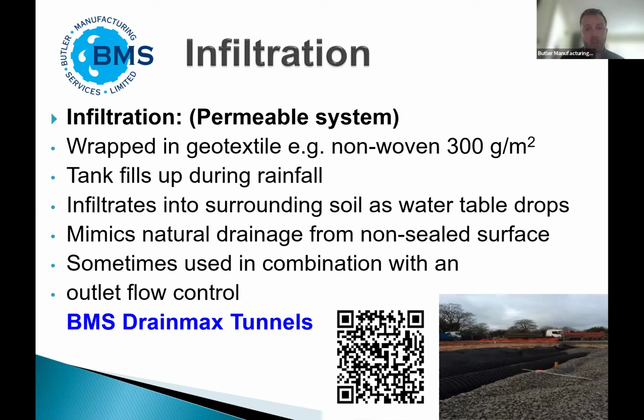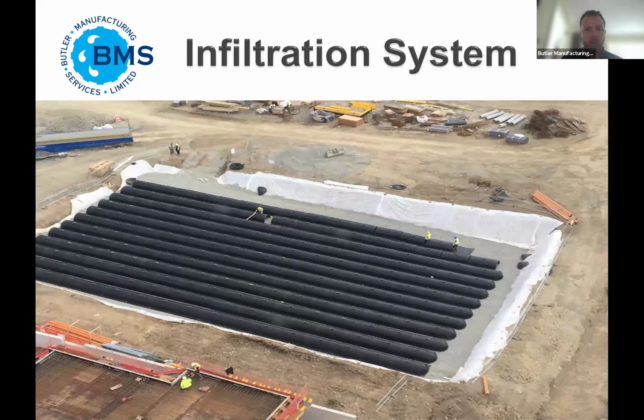Sometimes you can get a combination of the two, where you have an infiltration system but also include an outlet vortex flow control. So when it fills up, some water goes out via the sewage, and some infiltrates into the ground. So to sum it up: an attenuation system is an impermeable system, and an infiltration system is a permeable system.